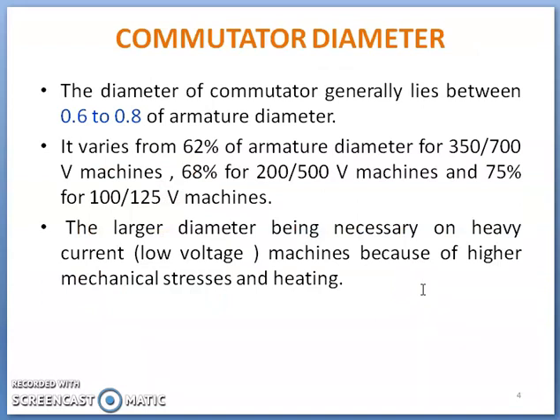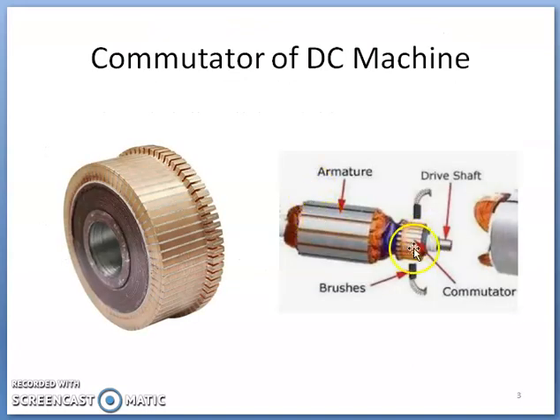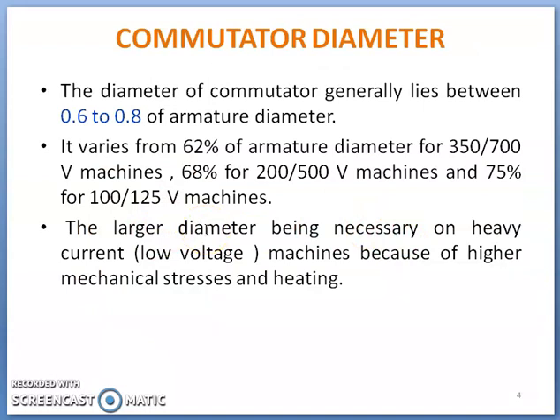Under commutator design, the diameter of the commutator is generally between 0.6 to 0.8 of the armature diameter. If the armature diameter is D, then the commutator diameter will be 0.6D to 0.8D. This ratio varies with voltage rating: 62% of armature diameter for 350–700 volt machines, 68% for 200–500 volt machines, and 75% for 100–125 volt machines.